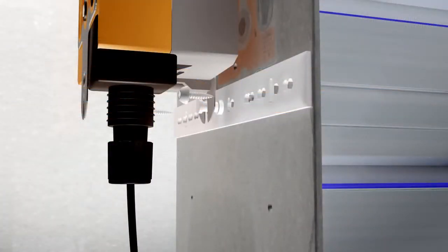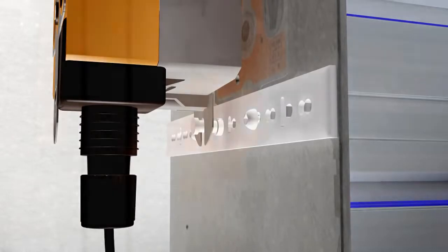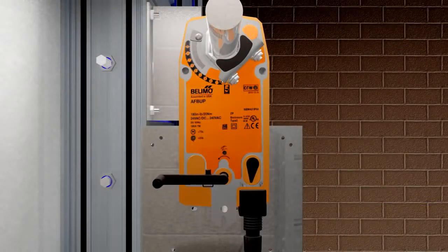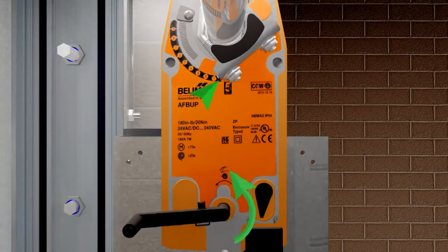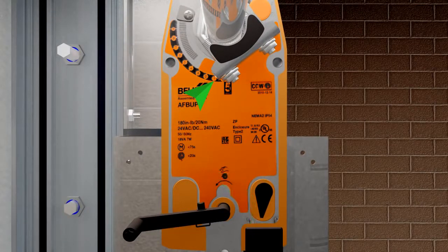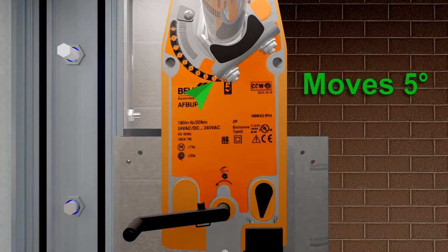Affix the anti-rotation strap to the mounting bracket. Insert the manual crank into the hexagonal slot on the face of the actuator and rotate the crank counterclockwise until the bottom edge of the universal clamp moves 5 degrees above the full fail-safe position which is at 0 degrees.